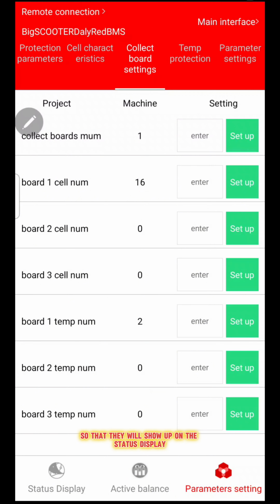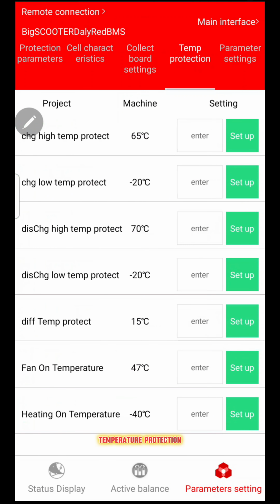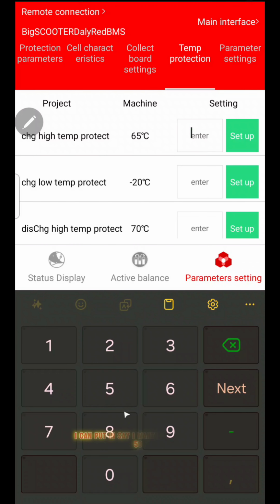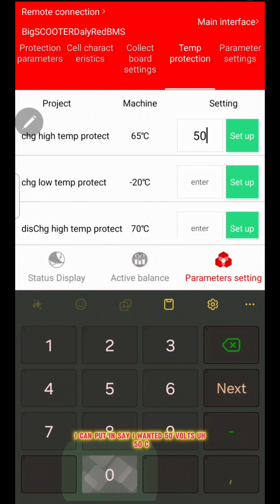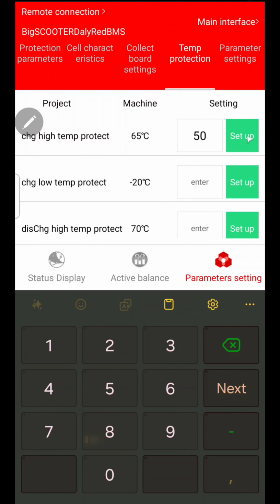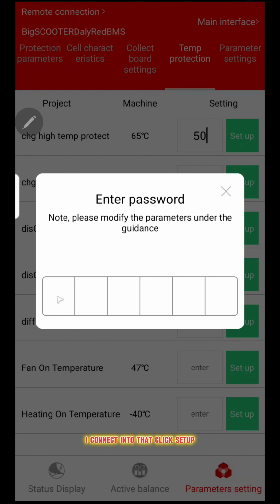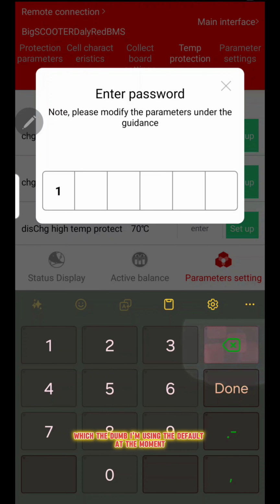Temperature protection, you can set your charge high temperature protection. And as I say, you can change all these parameters by putting your preferred value in the box here and hitting setup. So if I wanted to change that, I can click enter. I can put in, say I wanted 50 volts, 50C. I can enter that, click setup, have to put my password, which I'm using the default at the moment.